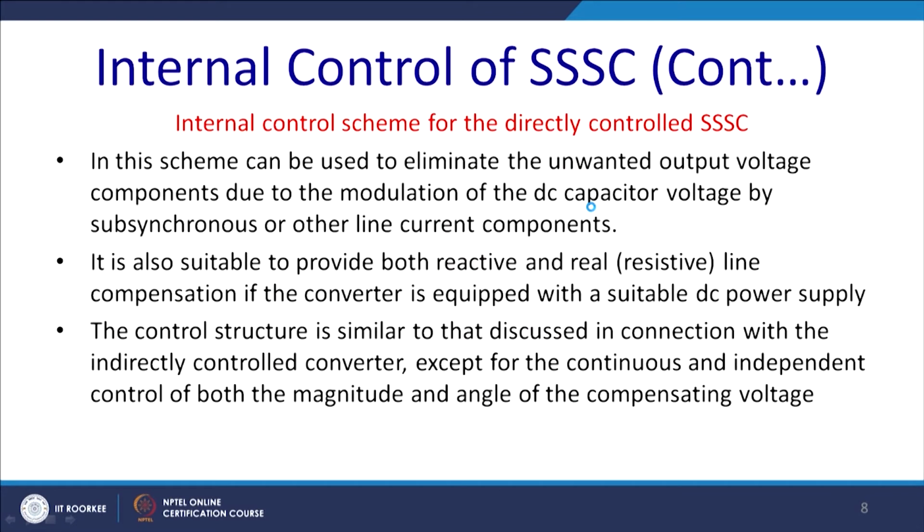From these discussions of the internal control technique, we can conclude this scheme can be used to eliminate the unwanted voltage component due to the modulation of the DC capacitor voltage by subsynchronous or other line components.